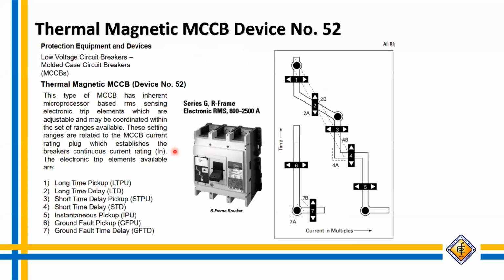So for the thermal magnetic, we have also different kinds of pickup and settings. For example, we have the long time pickup, also known as LTPU, long time delay, short time pickup, short time delay, instantaneous, and ground fault. So later we will have a brief explanation on those characteristics or tripping capabilities.